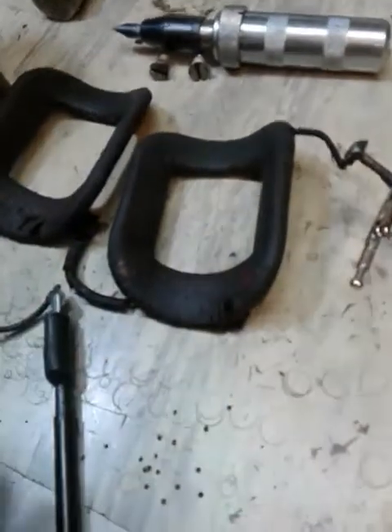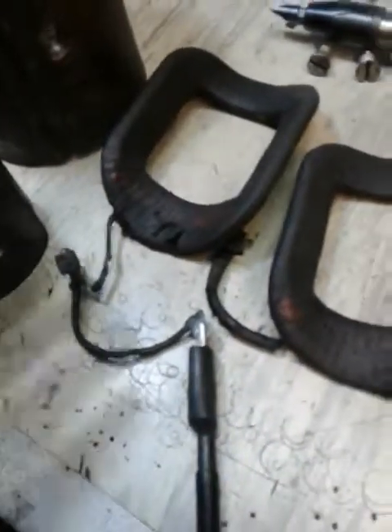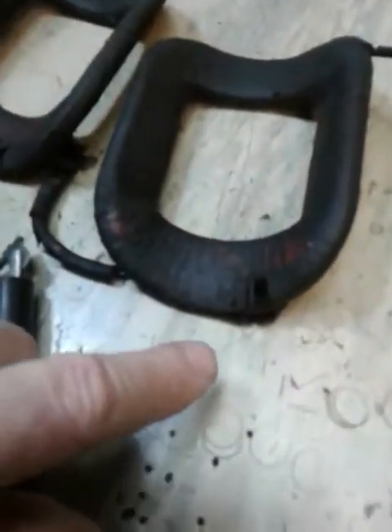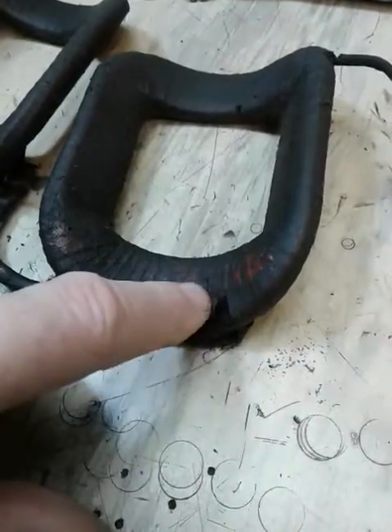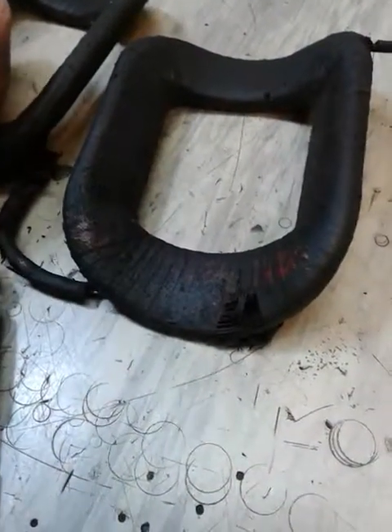The field coils are going to need to be rewrapped. They look to be in good shape but, as you can see if you try and focus here, the insulation that wraps them is deteriorating and coming off, so I'm going to rewrap these.